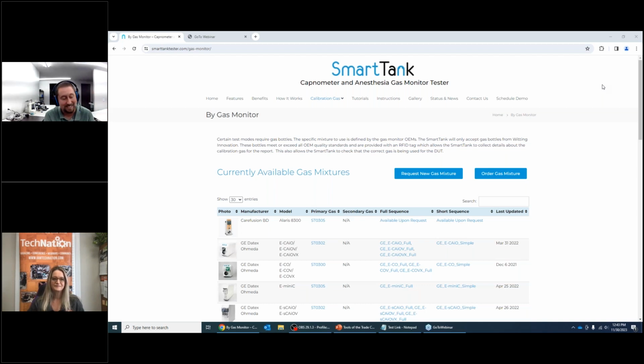So we actually can prevent you from calibrating with the wrong gas. If you're doing a sequence and it says put this gas bottle in, and you put the wrong gas bottle in, it will tell you and keep you from going on. It also records into the test the lot number and expiration date. So all that's documented, and you have full documentation of what was done. There are some tests, like the Philips 3015A full test, where you actually have to switch from 5% to 10% and you could forget. So it just helps you remember that.